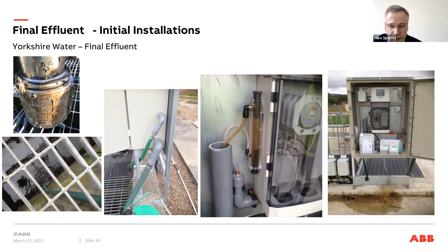One of the challenges we have - if you see the picture with the side pot in the middle, you can see how dirty that was. The interesting thing about ammonia monitors, especially ion selective ones, is they're quite robust and can take a high degree of debris before needing maintenance. But one lesson we learned is how to improve the system to allow it to run longer, greater than 3 months.